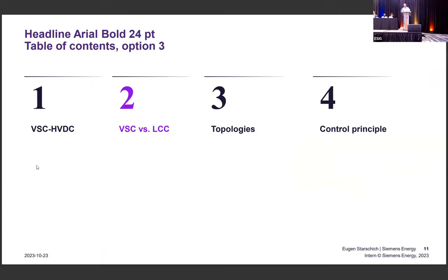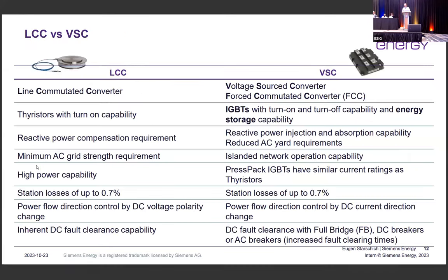And then, of course, we have been talking about VSC and LCC, so what are the key differences? Once again, LCC stands for line commutated converter, VSC for voltage source converter. To be exact, it's a force commutated converter. So we have line commutated converter and force commutated converter, but I think VSC is the most common one. The thyristors have only turn-on capability, while IGBTs have turn-on and turn-off capability. And this is one of the key factors. We have an energy storage capability.